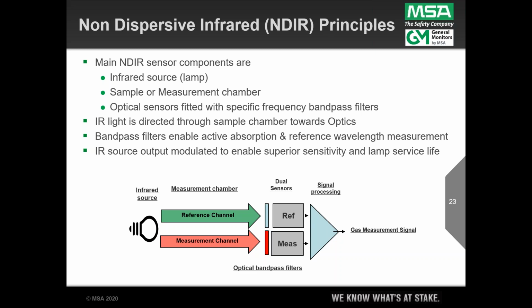not absorbed by hydrocarbon molecules. Basically, those signals go into a microprocessor where a ratio is calculated along with some other algorithm parameters defined in the Beer-Lambert law. We end up with a 4 to 20 milliamp signal proportional to the gas concentration in the measurement chamber. And I've got a little animation to show you that. So these devices are located in a site, and the whole premise is that the vapor of interest is going to impinge and fill up that measurement chamber and absorb that frequency of light on the active measurement band, and that enables detection to occur.